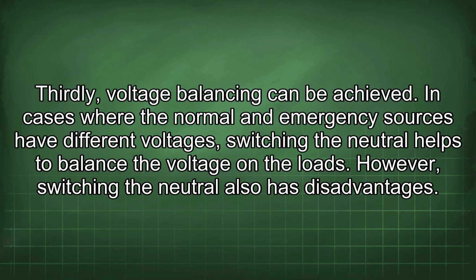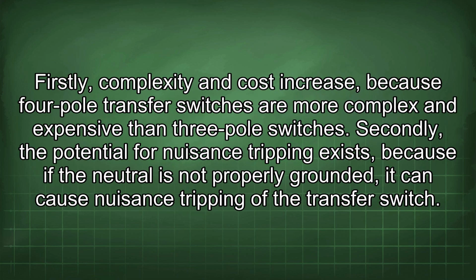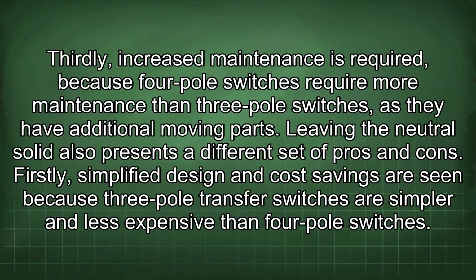However, switching the neutral also has disadvantages. Firstly, complexity and cost increase because 4-pole transfer switches are more complex and expensive than 3-pole switches. Secondly, the potential for nuisance tripping exists because if the neutral is not properly grounded, it can cause nuisance tripping of the transfer switch. Thirdly, increased maintenance is required because 4-pole switches require more maintenance than 3-pole switches as they have additional moving parts. Leaving the neutral solid also presents a different set of pros and cons.